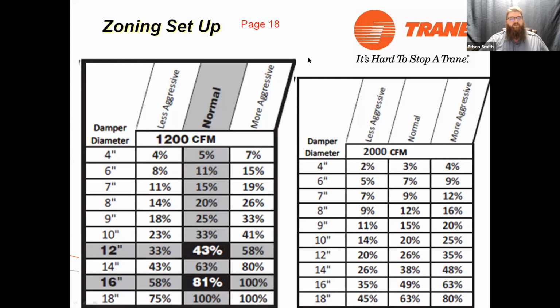Okay, this is just some rules of thumb, guys. If you don't have the static pressure sensor, or your ductwork won't accommodate the static pressure sensor, these are generic tables you can find out there. This one's actually right out of the zoning manual. It gives you various CFMs for total system CFM, and it will tell you approximately what that 12-inch run is going to take, what that 6-inch run is going to take. And it gives you a percentage of that CFM. So you take 1200, multiply it by 11%, you're going to come out roughly 125 CFM for that 6-inch duct.